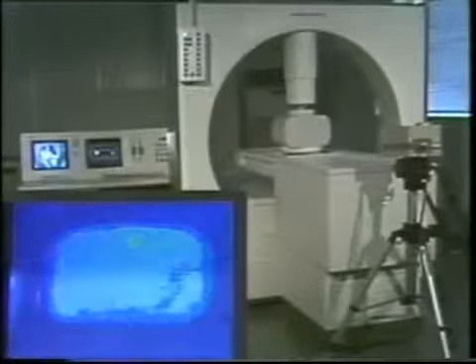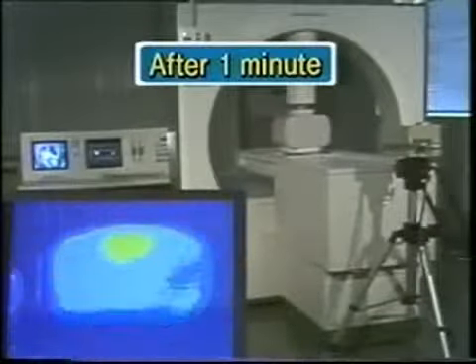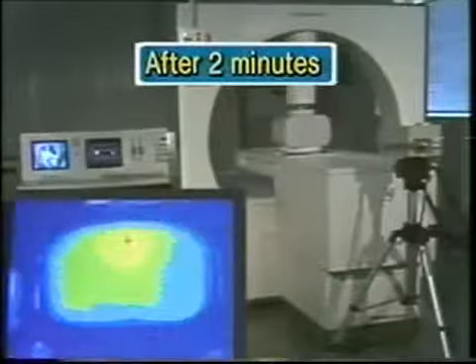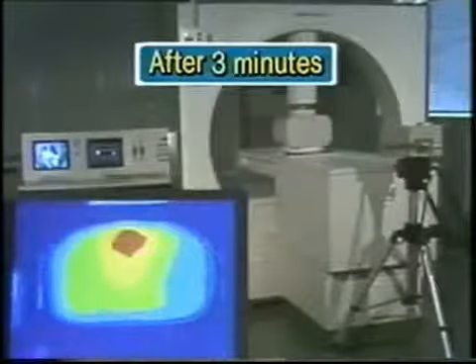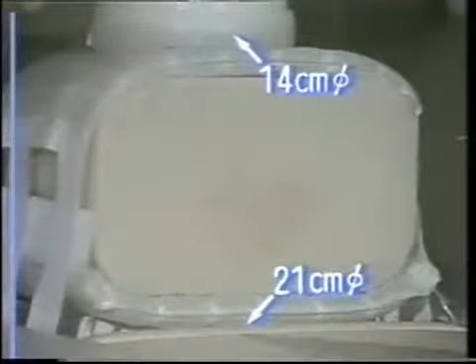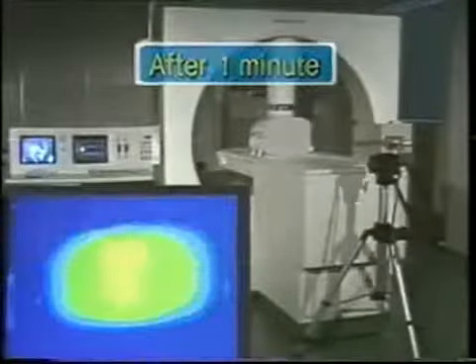The blue color before heating represents about 36 degrees centigrade. The color begins to change following elevation of the temperature. Green represents 39 degrees, yellow 41 degrees, and red 43 degrees centigrade. Electrodes of 14 centimeters and 21 centimeters in diameter can selectively heat subsurface or relatively shallow areas. An area 5 to 6 centimeters under the surface is substantially heated.